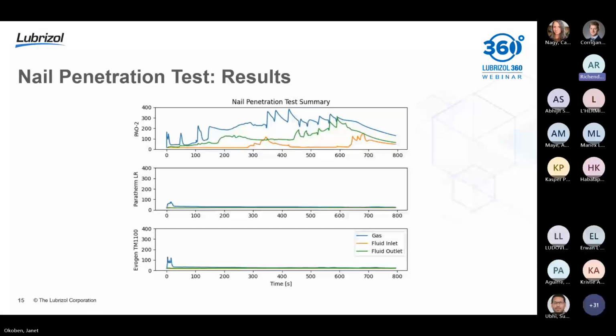That gas is usually released at a very hot temperature, 400 Celsius and above. It's a very good indicator of when one of these cells has entered thermal runaway. If you look at the PAO2 base oil, you can see each of the 12 spikes that occur, meaning each of the 12 cells went into thermal runaway at one point during the test. It's very clear.